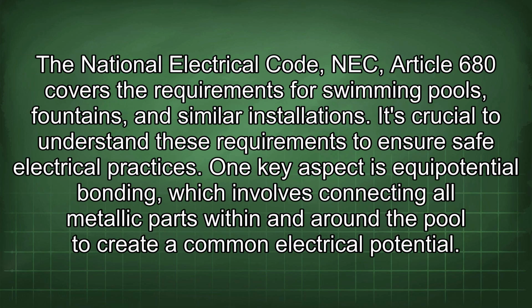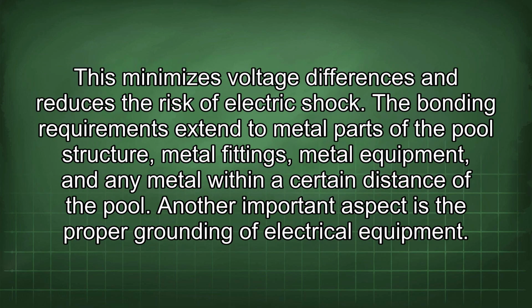The National Electrical Code, NEC, Article 680 covers the requirements for swimming pools, fountains, and similar installations. It's crucial to understand these requirements to ensure safe electrical practices. One key aspect is equipotential bonding, which involves connecting all metallic parts within and around the pool to create a common electrical potential. This minimizes voltage differences and reduces the risk of electric shock. The bonding requirements extend to metal parts of the pool structure, metal fittings, metal equipment, and any metal within a certain distance of the pool. Another important aspect is the proper grounding of electrical equipment.